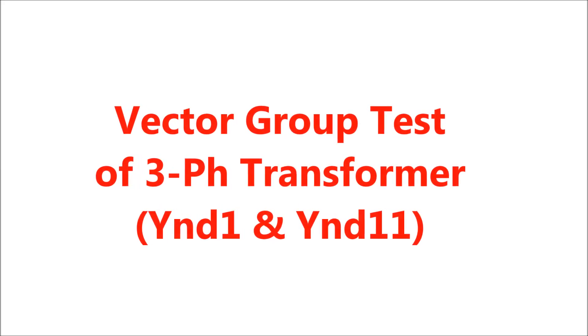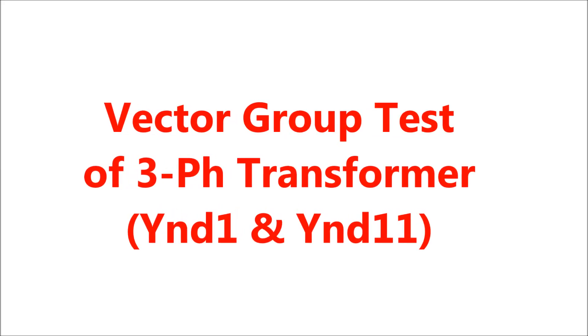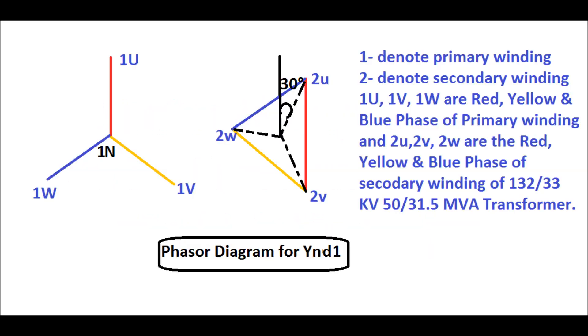This video covers the vector group test of three-phase transformers YND1 and YND11. The phasor diagram for the YND1 power transformer is shown in this figure. Here, '1' denotes the primary winding or HV winding of a power transformer, and '2' denotes the secondary winding or LV winding of the power transformer. 1U, 1V, and 1W in capital letters represent the red, yellow, and blue phases respectively.